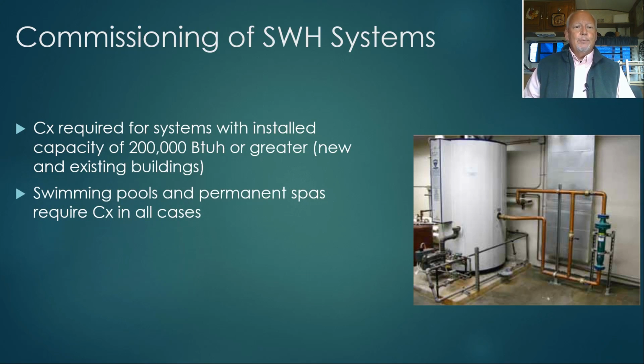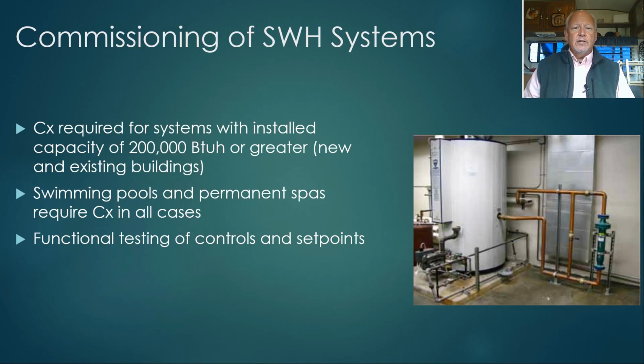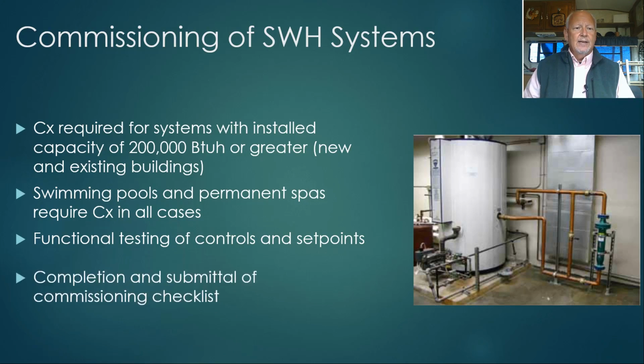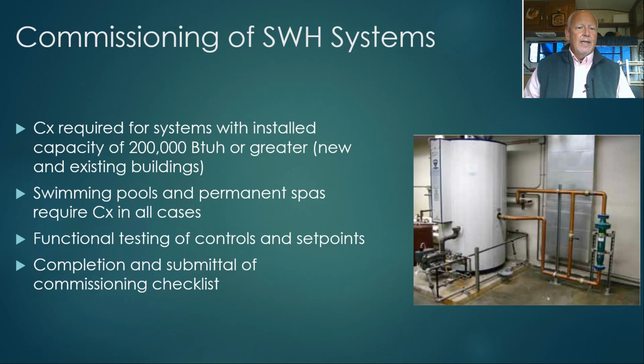Well, first of all, swimming pools and permanent spas require commissioning in all cases, regardless of heating equipment size. The scope of commissioning includes functional testing of controls and set points, and finally, completion and submittal of the commissioning checklist, which you can find a copy of in the Washington State Energy Code.